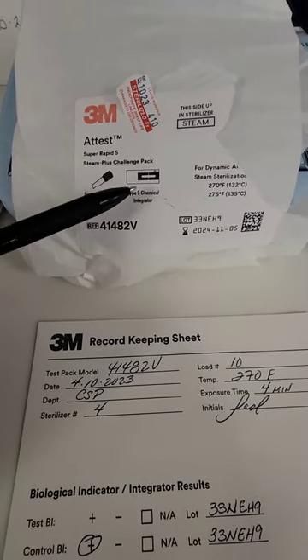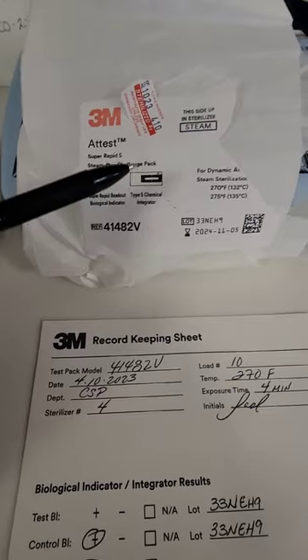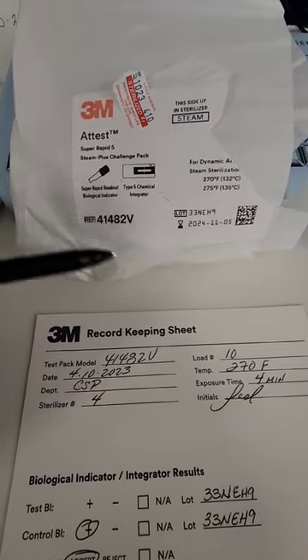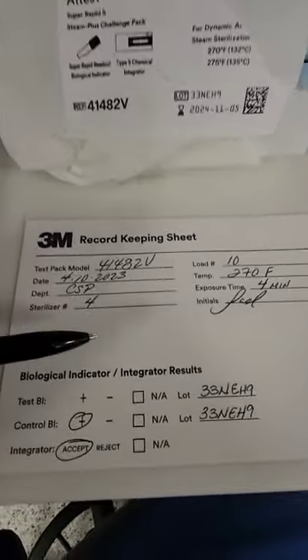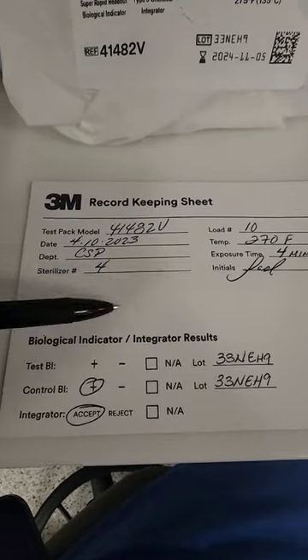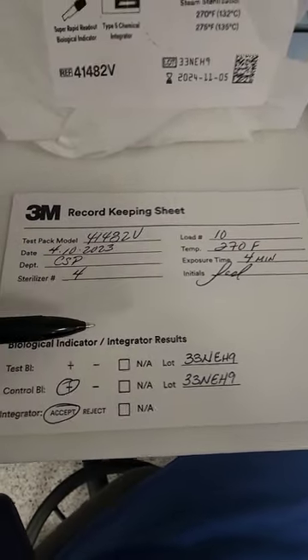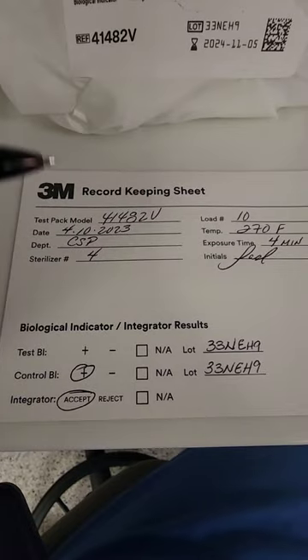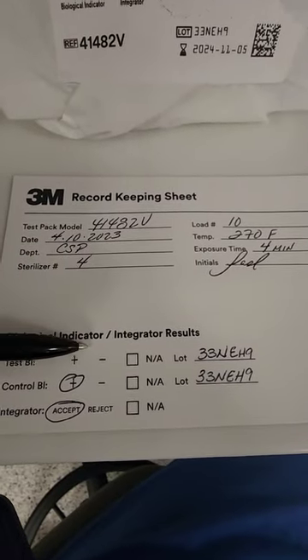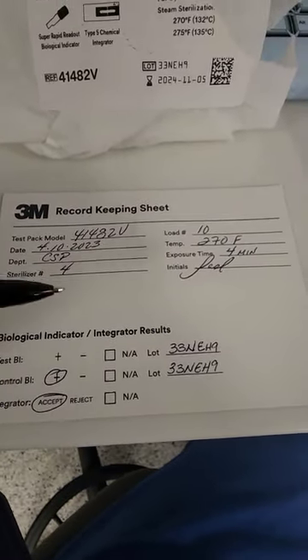They would all be considered PCD depending on what you use to release your load. Now, if it's an implant, it should always be a biological. But for a regular load, it can just be a chemical indicator. All right, so all that information is documented on this little card for your records.